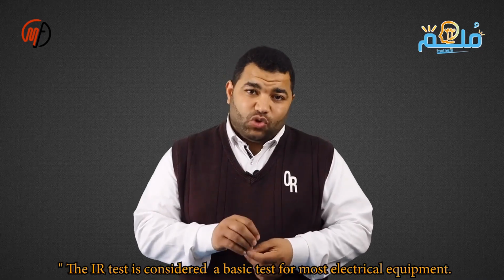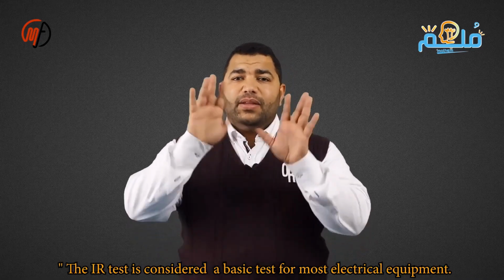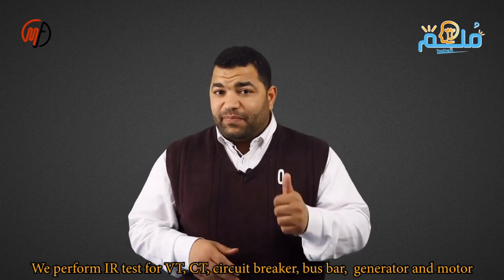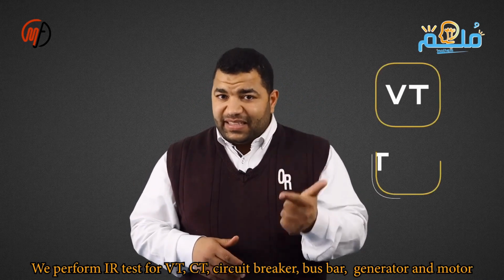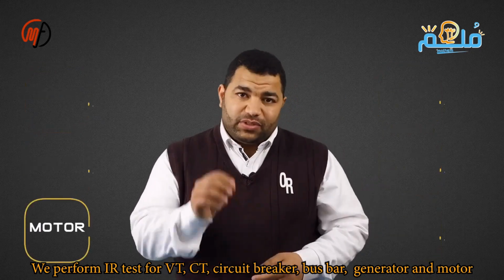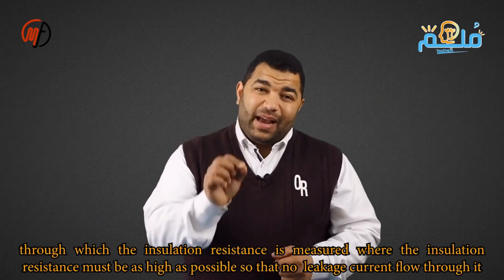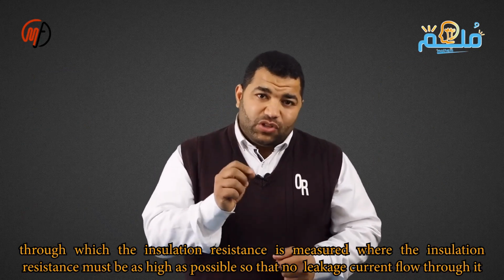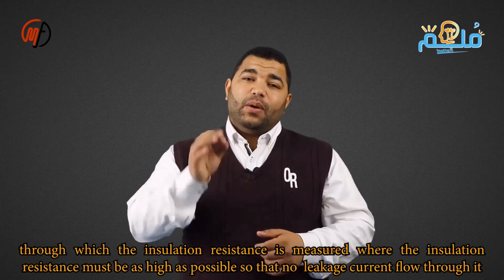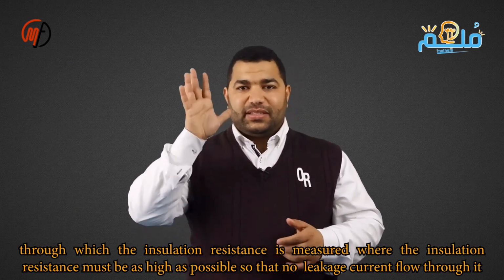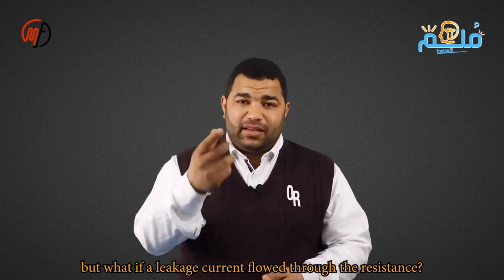The IR test is crucial for electrical equipment. It measures high insulation resistance to prevent leakage current. Leakage indicates insulation failure, a dangerous short circuit, measured in giga or tera ohms, with leakage in milliamps. The IR test uses a Megger to apply DC voltage: 5 kV from primary to ground, 2.5 kV from primary to secondary, and 1 kV from secondary to ground.